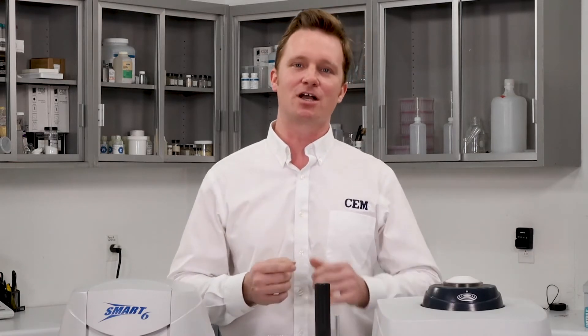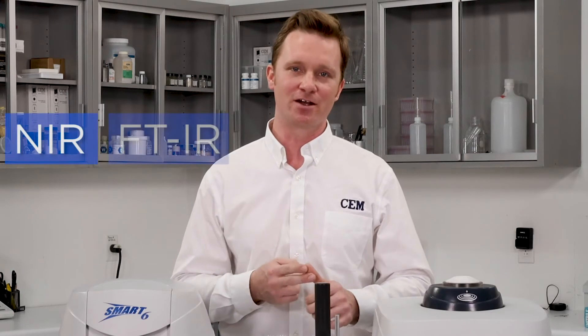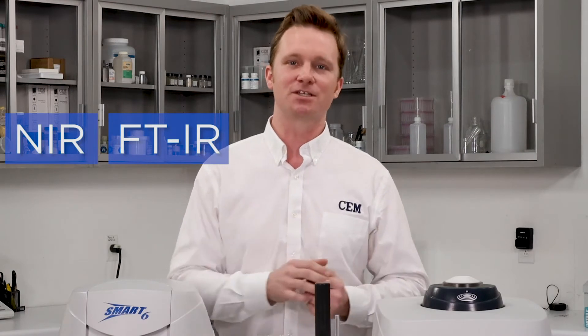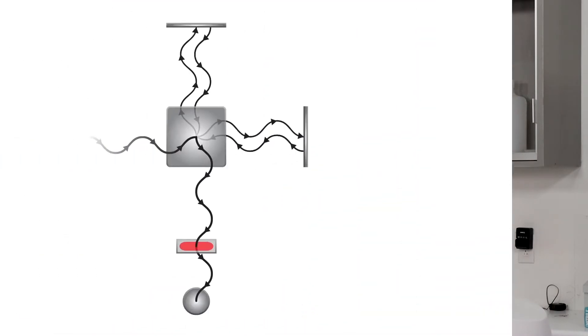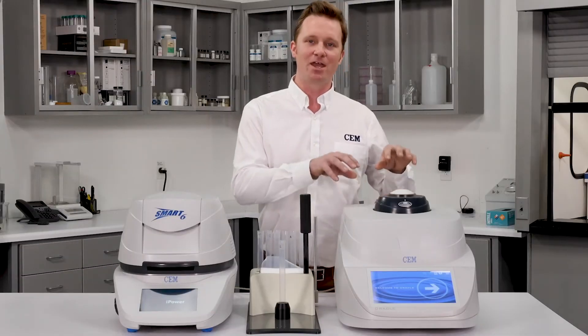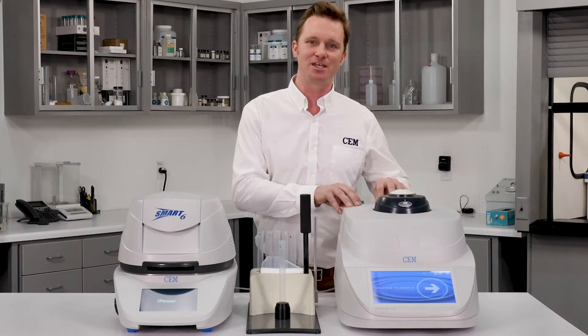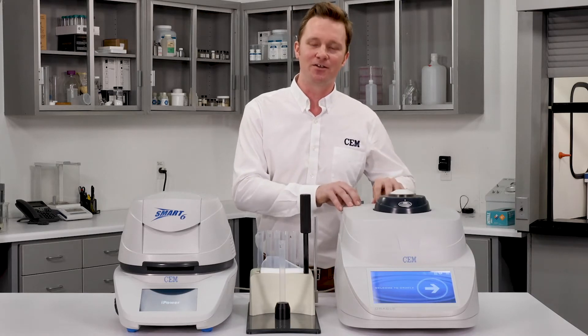Now let's take a broader look at how the Oracle compares to other rapid fat analyzers on the market — specifically NIR and FTIR. These are both spectroscopic methods that take an optical signal and through chemometrics generate a fat result. The issue is they have a complex optical train that requires constant recalibration to maintain accuracy, whereas the Oracle has no moving parts and maintains reference-level accuracy day in and day out.